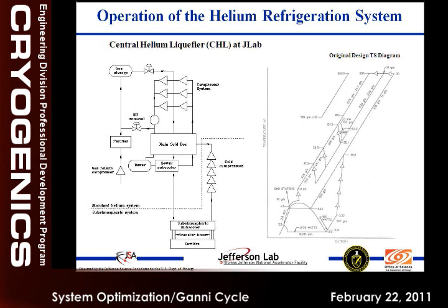If you are going to put this much power, say your design capacity, let's say CHL, we need 4.6 kilowatts at 2 Kelvin. So it comes with a certain amount of Carnot work, so much in terms of the compressor power and cold wall size. So what we should envision at that time is to make sure the machine is also doing the 2K. If it happened that we need a 4K, is it producing all the capacity it can produce at 4K, or is some silly valve or silly pipe limiting it? If we don't go through all the modes, you won't recognize what a simple, small thing can restrict it. And I'll go over the real-life examples where we got caught ourselves.